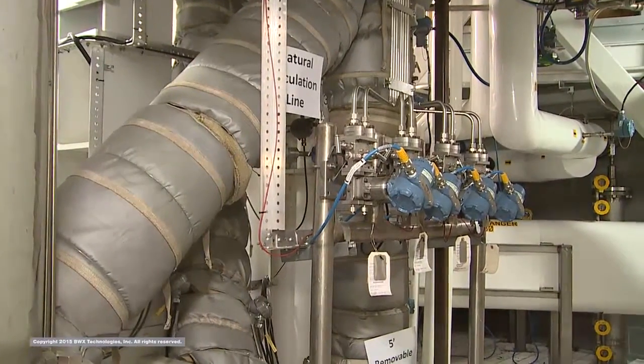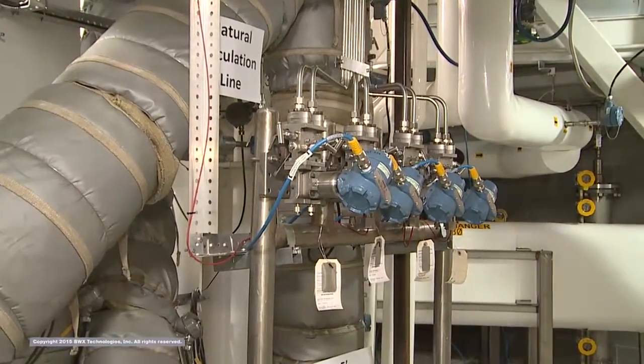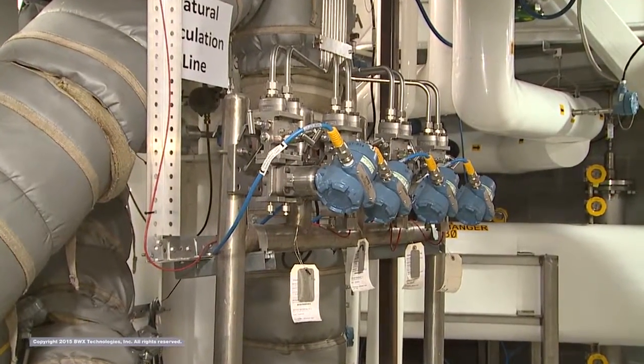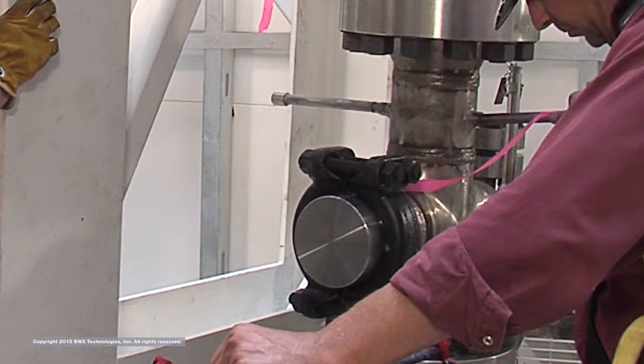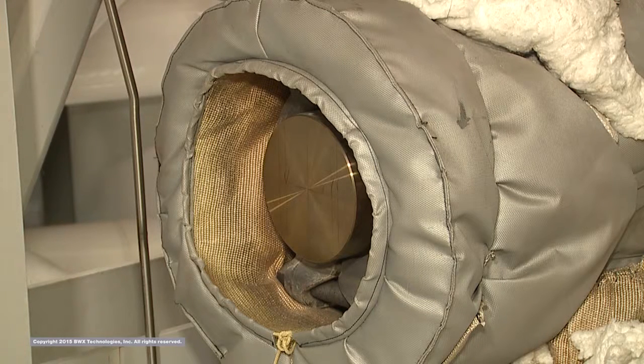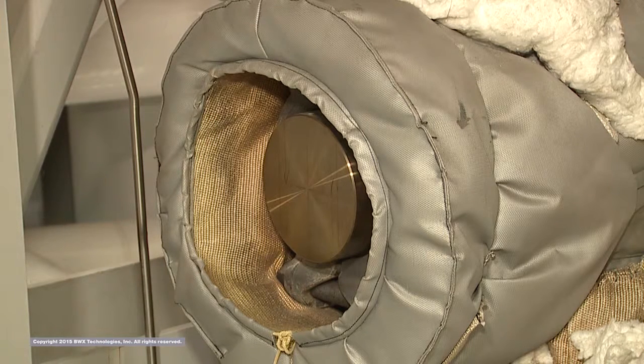The riser is fully instrumented with differential pressure transmitters and RTDs detecting process conditions. At the top of the riser, directly above the steam generator, a 5-inch diameter flanged instrument connection is also available for installation of additional instruments in the primary system. This location can, among other things, provide a location to investigate primary to secondary heat transfer of the steam generator for code validation or provide a monitoring point for transient phenomena between the riser, pressurizer, and primary side of the steam generator.